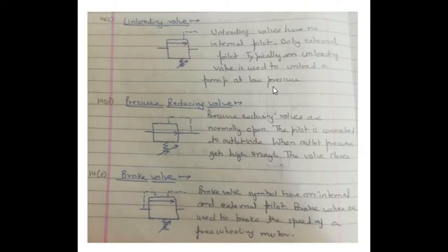14D pressure reducing valve. Pressure reducing valves are normally open. The pilot is connected to the outlet side of the port. When pressure, that is outlet pressure, gets high enough, the valve closes.